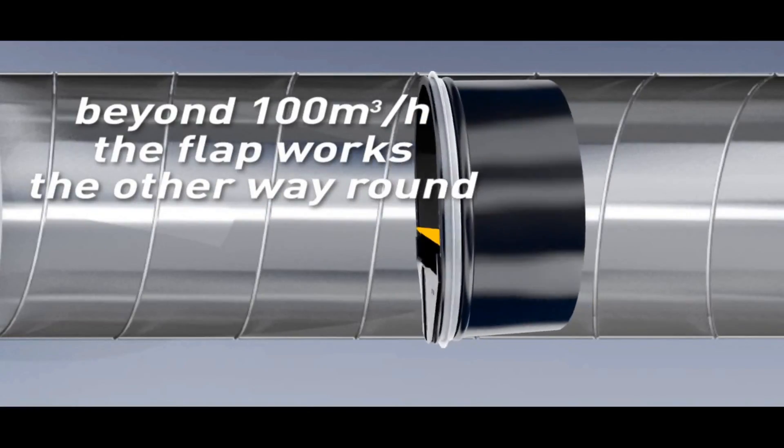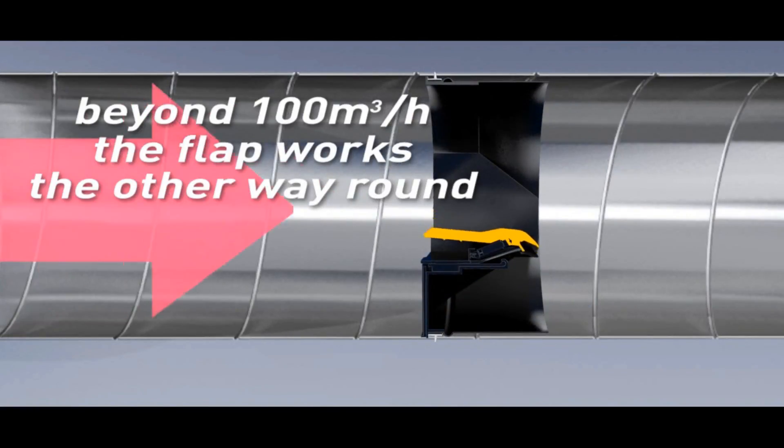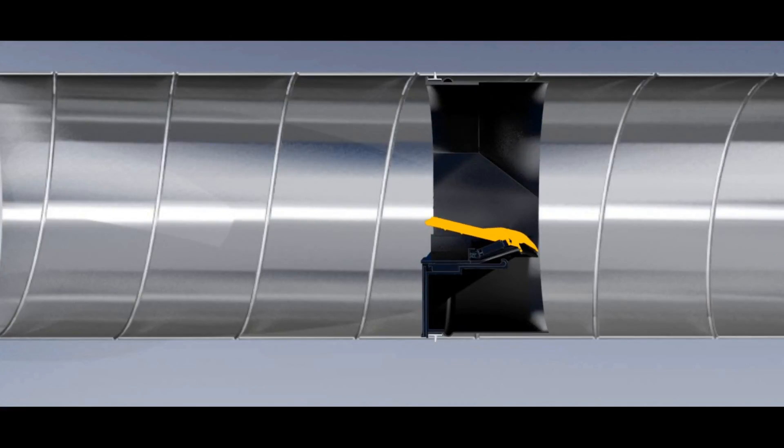For flow rates superior to 100 cubic meter per hour, the flap works the other way round. The front of the flap rises to regulate the air flow rate according to the pressure.